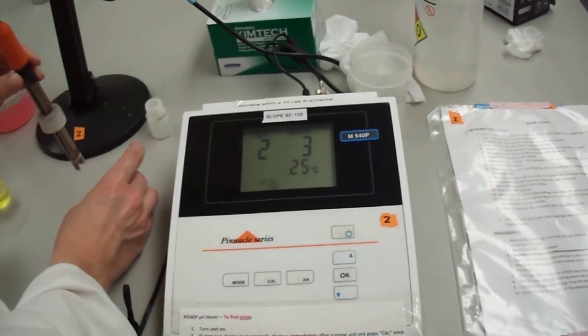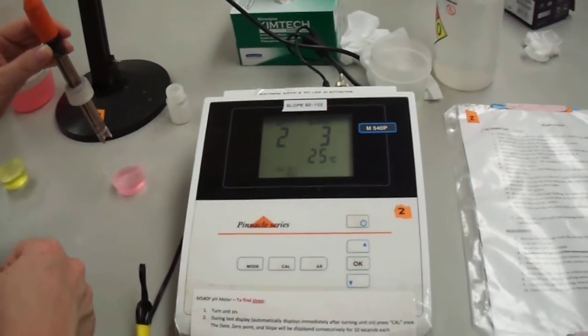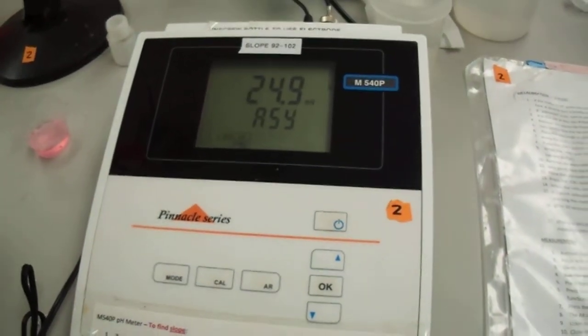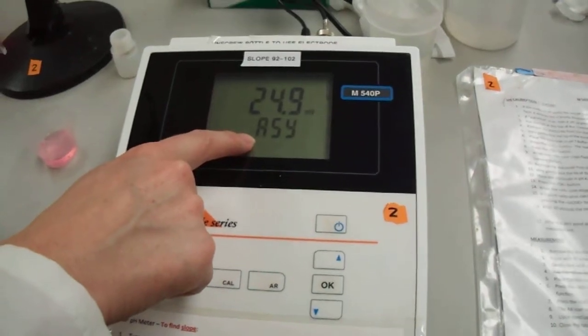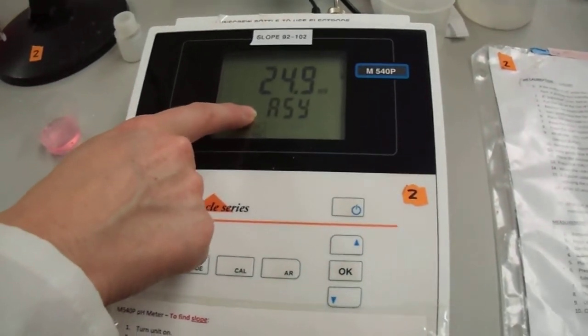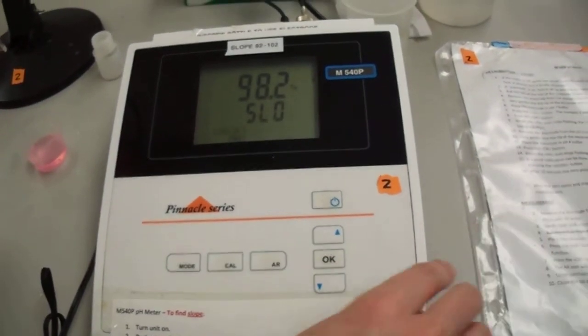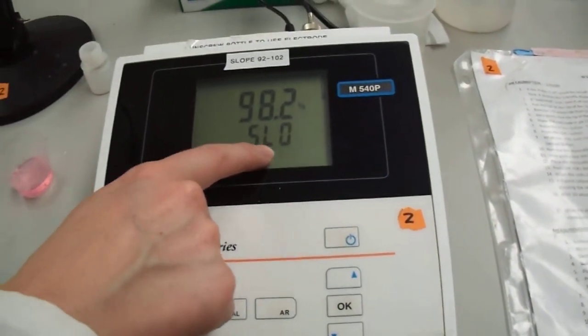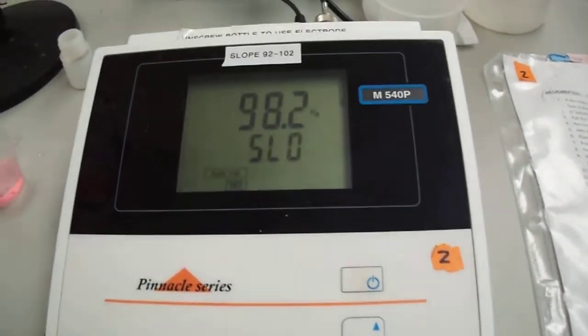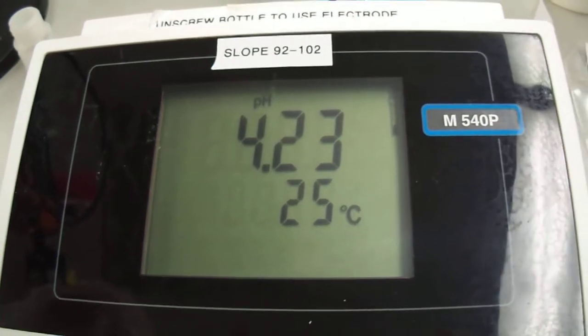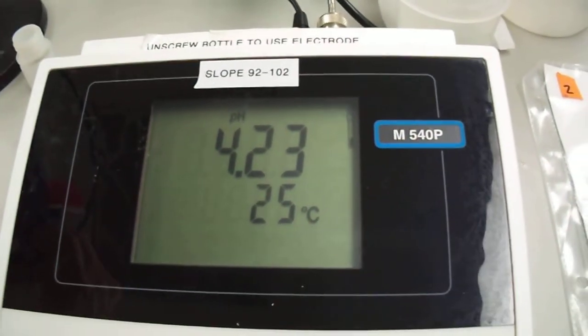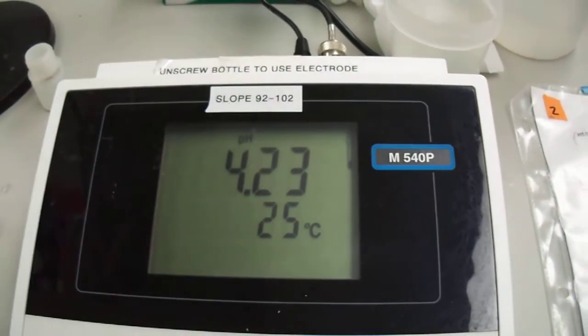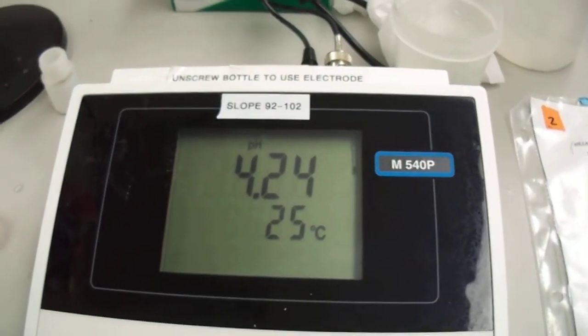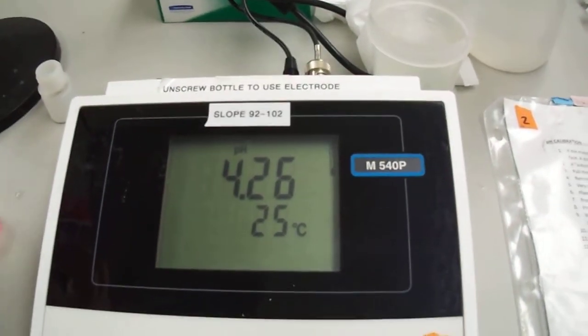Now what? After 10 seconds, the 0 point ASY will be displayed. Oh, you need to conclude by pressing the mode button. Then after 10 seconds, the 0 point ASY will be displayed. Okay. Which we're not concerned with at this point in time. We're concerned with the slope, which will appear after 10 seconds. So this is SLO, which is our slope, and you can see here that it reads 98.2. In order for us to proceed with testing, the slope should read somewhere between 92 and 102. So this piece of equipment is in calibration, and we may proceed with the testing of our sample.